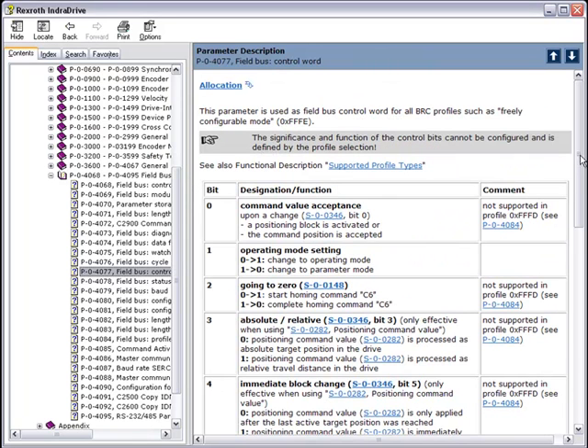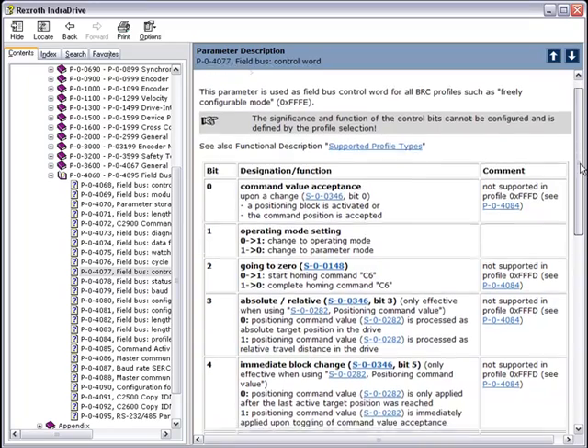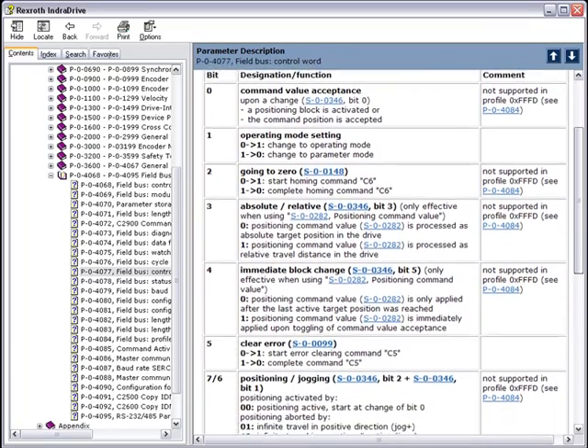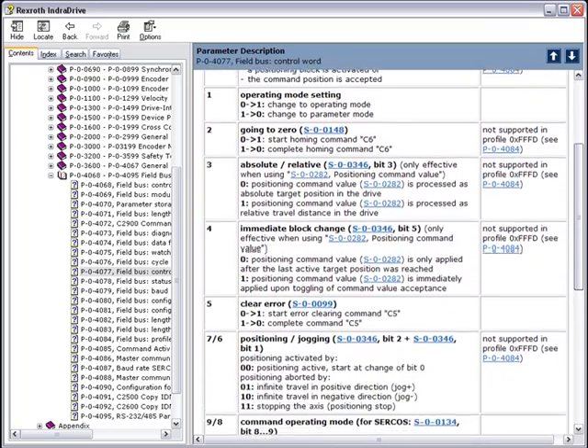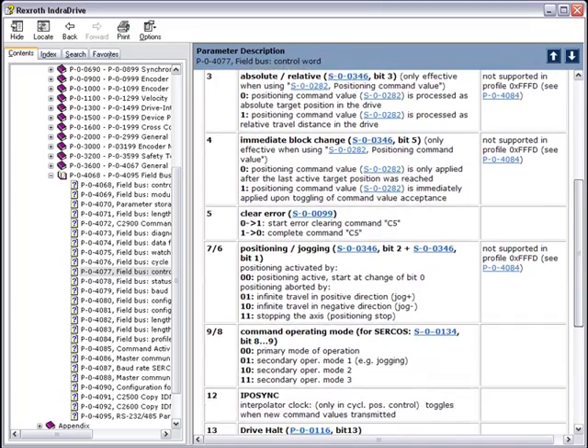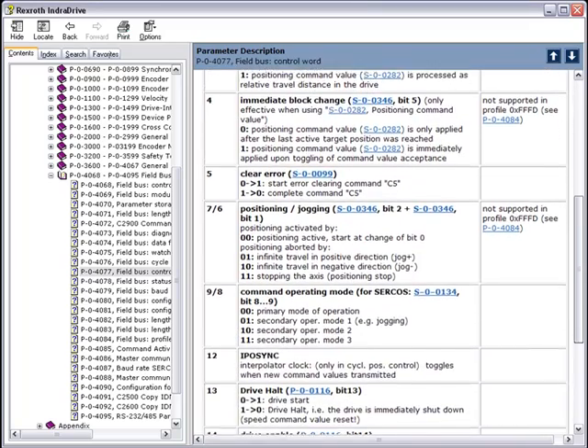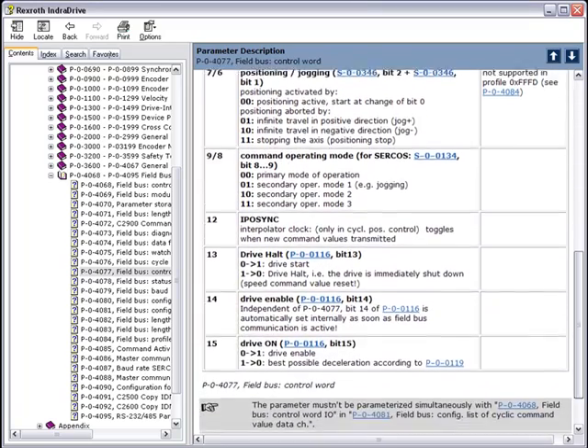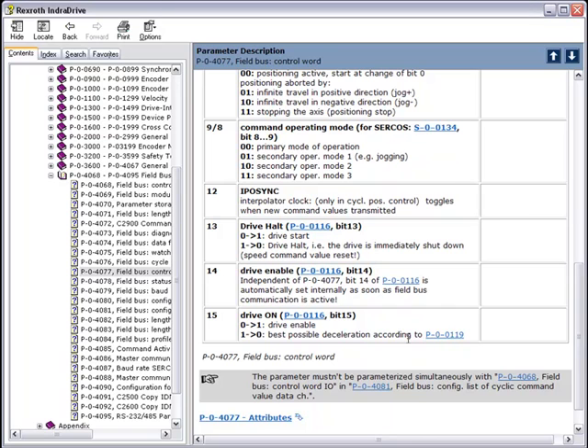The P4077 parameter is our control word. The help file will break down bit by bit how that parameter controls the drive. From here we can see that turning on bit 15 and 14 will enable our drive. Turning on 13 will allow the drive to move by removing the drive halt.